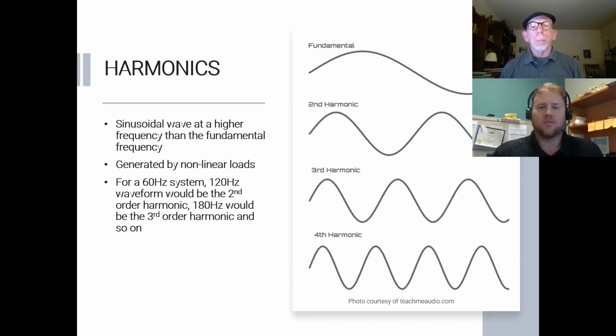So in a perfect world, if you're getting completely linear loads all around you in your facility, and the same on the lines around you, you're going to have only the 60 hertz sine wave. But in reality, what you may see at your equipment is a 60 hertz frequency wave, a 120 hertz wave, a 180 hertz wave, and on and on and on.